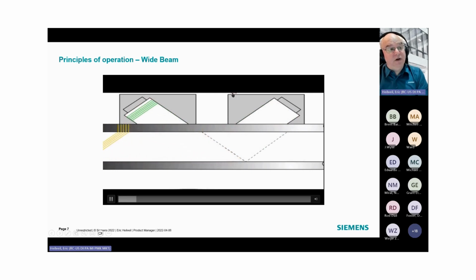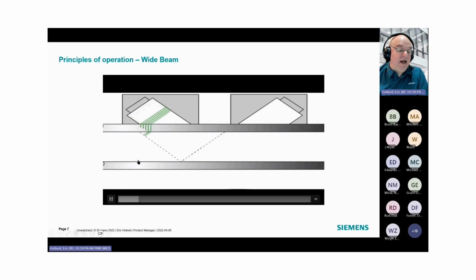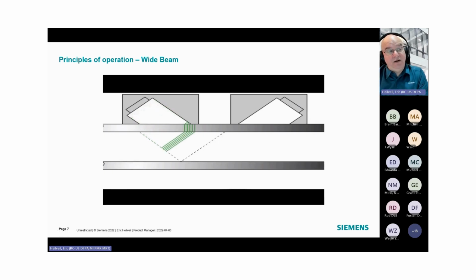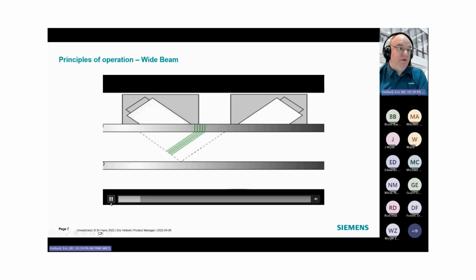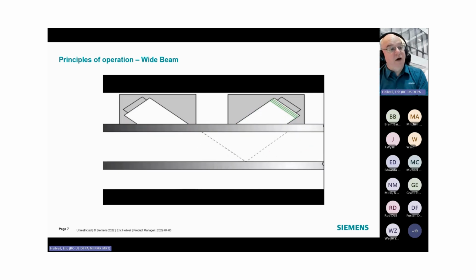Now, if there's a no flow condition, the upstream and the downstream flow will be at exactly the same pace, at exactly the same time. So the time downstream will be the same as the time upstream. But as soon as there's a current, or in this case, a flow, the flow rate can be determined by the time difference of the reflection of the upstream versus downstream flow. It's really that simple. So it's all a matter of how fast the time it takes to go against the current.